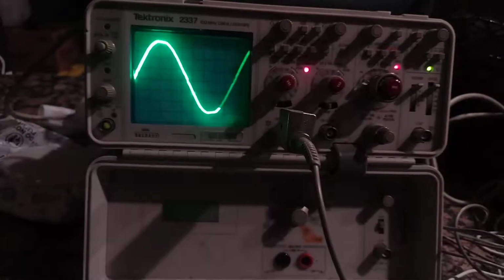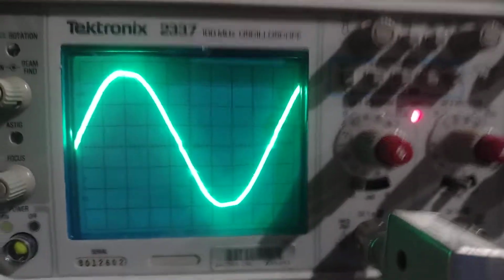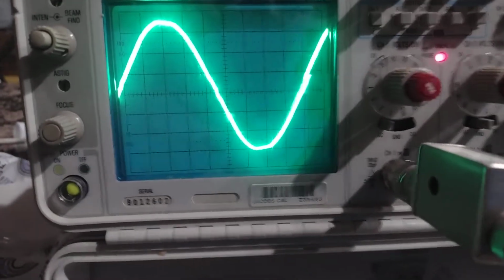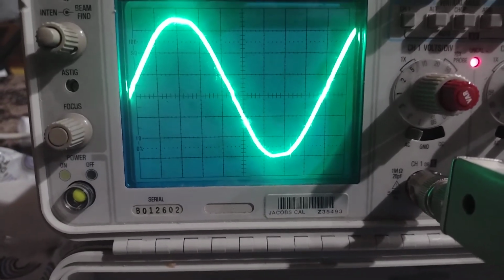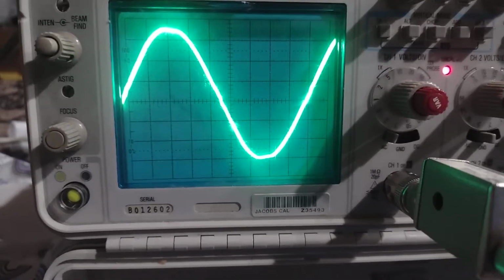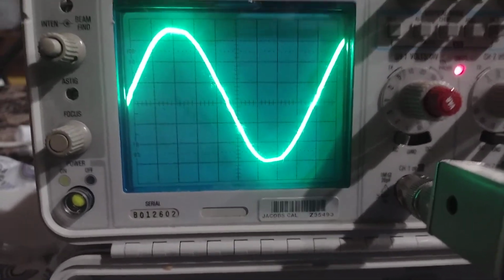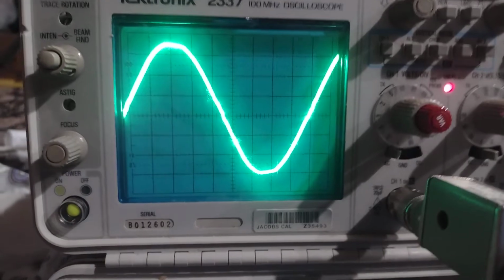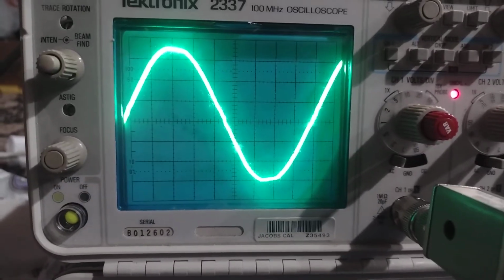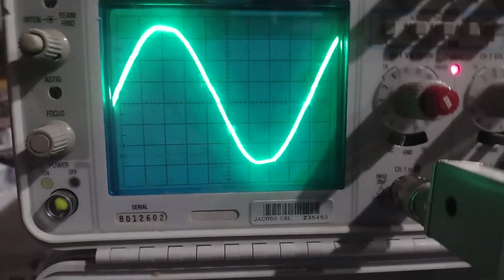That ain't bad. Turn that off. It's a little flat at the top and the bottom, but that ain't bad. I'd be willing to call that less than 10% total harmonic distortion - maybe even 15% total harmonic distortion, but I'm okay with that.